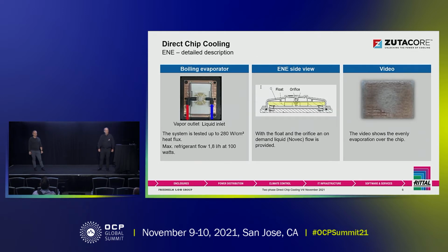The main point and the main difference that ZutaCore has brought into the market is the evaporator cold plate. This cold plate works on the chip exactly like a water-based one, but it doesn't include water. The liquid that flows inside is a completely dielectric liquid. There's no chance of it hurting or harming the IT, the servers. The liquid goes into a very thin tube, 4mm tubes. It fills in a pool.